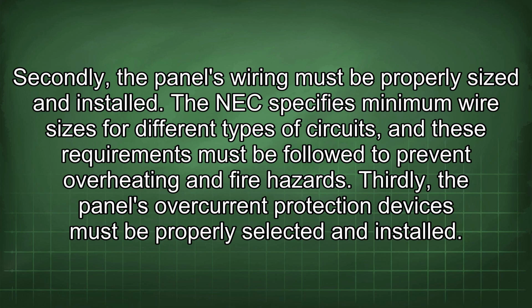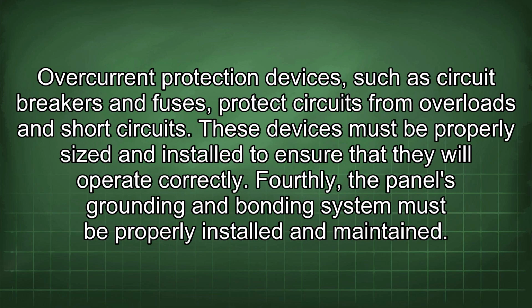The NEC specifies minimum wire sizes for different types of circuits, and these requirements must be followed to prevent overheating and fire hazards. Thirdly, the panel's overcurrent protection devices must be properly selected and installed. Overcurrent protection devices, such as circuit breakers and fuses, protect circuits from overloads and short circuits. These devices must be properly sized and installed to ensure that they will operate correctly.